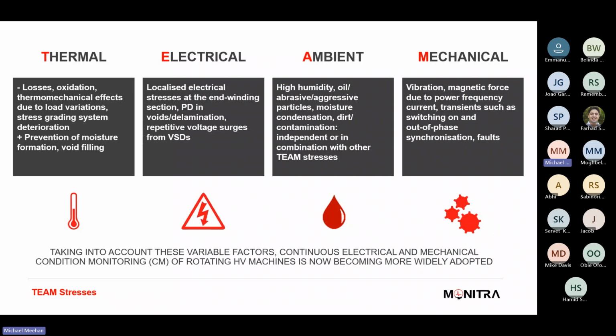The electrical stresses, so localized electrical stresses at the end winding section, there's a lot more stresses in that end winding region, potentially more vibration, depending if the end winding is being supported accordingly and sufficiently. Vibrations can lead to wear. When that insulation wears, you end up with stresses, and that's when you can end up with PD activity and issues with the insulation.